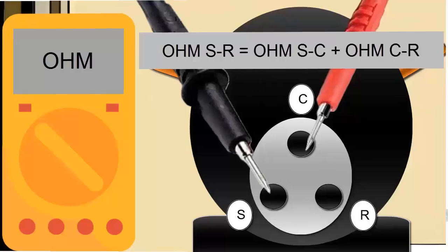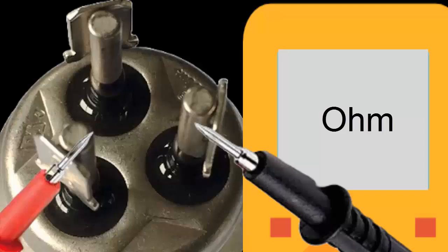6. For inverter compressors, the resistance between each pair of pins must be identical. Use a multimeter set to ohms to perform this test.